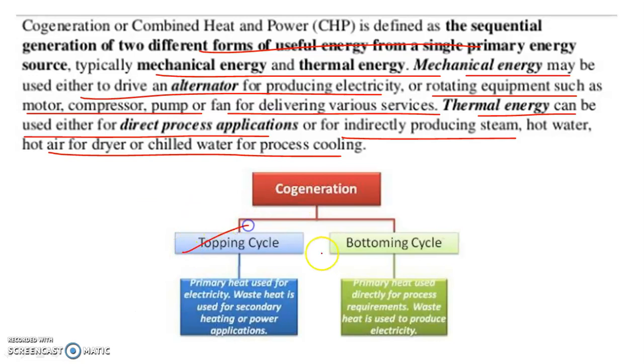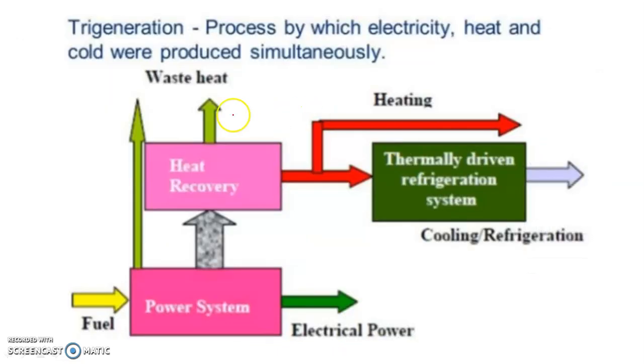Cogeneration is of two types, topping cycle and bottoming cycle. Topping cycle, what is happening? Primary heat is used for electricity, and waste heat is used for secondary heating or power applications. In the bottoming cycle, primary heat is used directly for process requirements and waste heat is used to produce electricity. Trigeneration means a process by which electricity, heat and cold are produced simultaneously. So this figure is indicating trigeneration. Fuel is given to the power system, which produces electric power here. Then there is heat recovery, which is used in cooling, refrigeration as well as for heating. So trigeneration: heating, cooling and electric power.